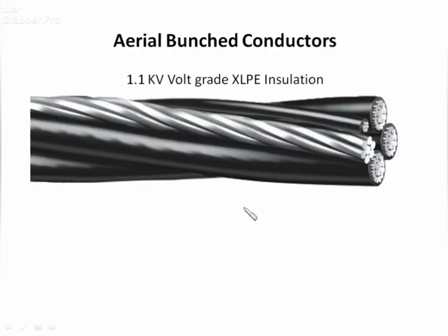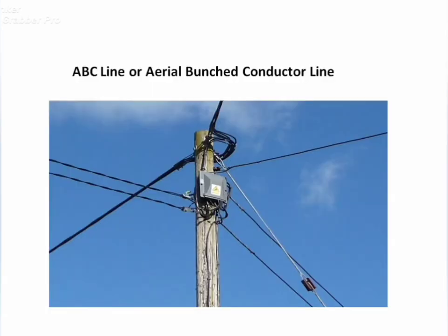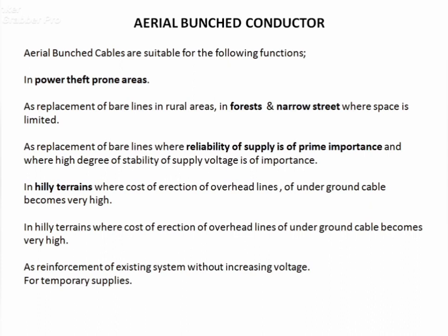Now we will look at Aerial Bunched Conductor (ABC). You can see a picture of 1.1 kV XLPE insulated bunched conductor — the neutral or messenger conductor and the phase conductors are bundled. ABC is mostly used to avoid theft; a 1.1 kV XLPE insulated ABC makes it very difficult to illegally hook into. Benefits include use in power theft-prone areas, forests, narrow streets, hilly terrain, and other areas.